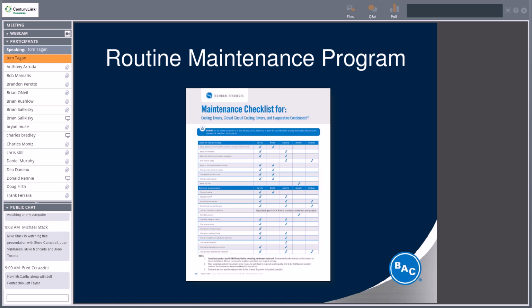Inspect the air intake louvers. The cooling tower is the world's greatest air scrubber. So whatever is in the air, whether your tower's on grade or on the roof, it's going to be pulling in any debris or leaves or things of that matter. So keeping the basin clean is very important to keep the efficiency of your system going, to keep the chemicals in your cooling tower working properly.